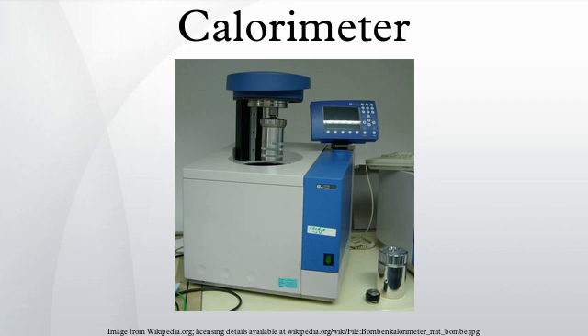An adiabatic calorimeter is a calorimeter used to examine a runaway reaction. Since the calorimeter runs in an adiabatic environment, any heat generated by the material sample under test causes the sample to increase in temperature, thus fueling the reaction. No adiabatic calorimeter is fully adiabatic — some heat will be lost by the sample to the sample holder. A mathematical correction factor, known as the phi factor, can be used to adjust the calorimetric result to account for these heat losses.